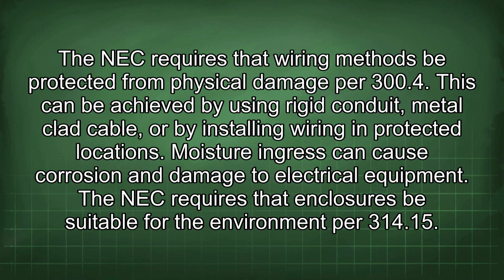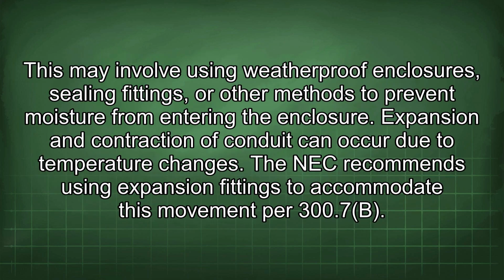Moisture ingress can cause corrosion and damage to electrical equipment. The NEC requires that enclosures be suitable for the environment per 314.15. This may involve using weatherproof enclosures, sealing fittings, or other methods to prevent moisture from entering the enclosure. Expansion and contraction of conduit can occur due to temperature changes. The NEC recommends using expansion fittings to accommodate this movement per 300.7(B).